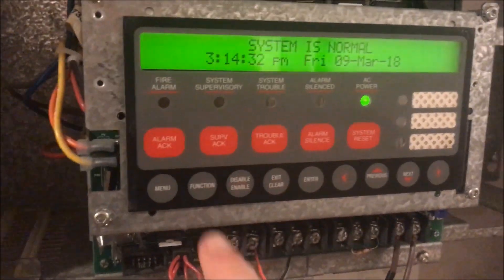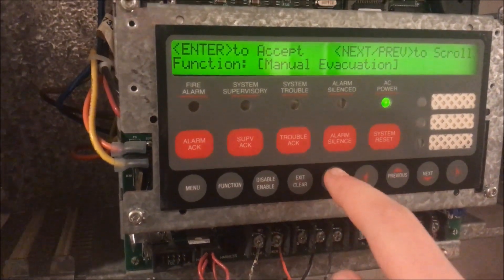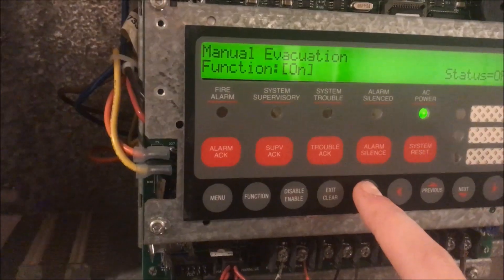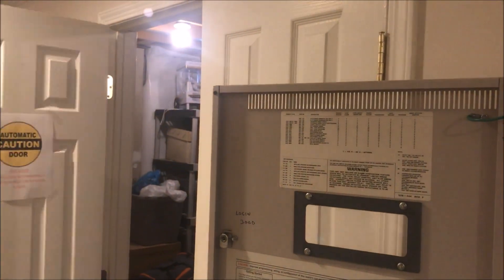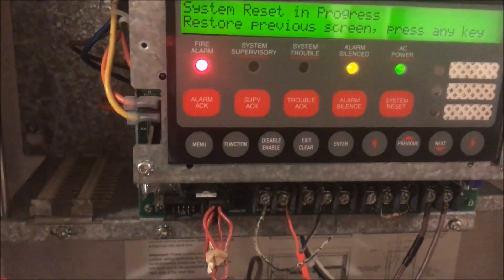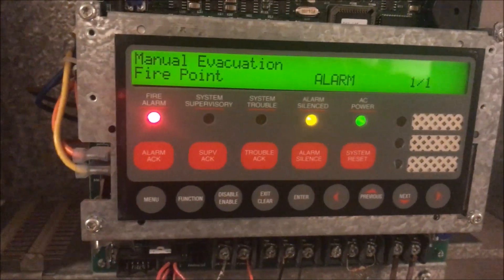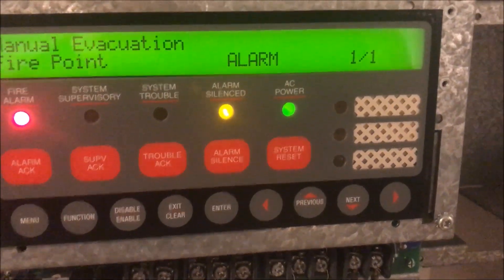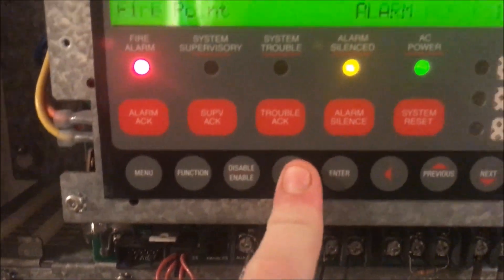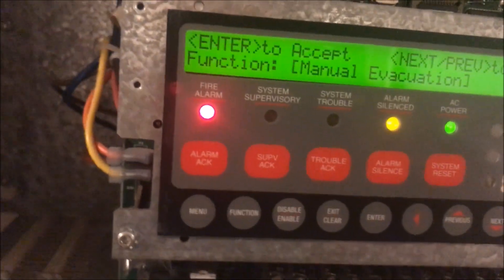Starting again with the function button in level three — look at that, we can now do a manual evacuation. You can set it to on and we'll open the door. Hitting manual evac and turning it on basically starts a fire drill. Also, anything you can do in a previous level you can do in the next level up plus more — it's not an either/or situation.